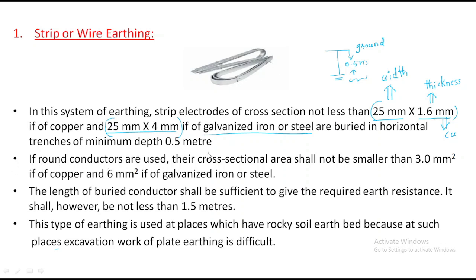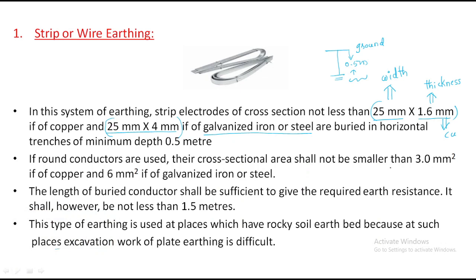If round conductors are used, the cross-sectional area shall not be smaller than 3 mm square. What is cross-sectional area? If we are using round conductors, the cross-sectional area formula is pi r square, and that must be not less than 3 mm square if copper is used, and 6 mm square if galvanized iron or steel is used.